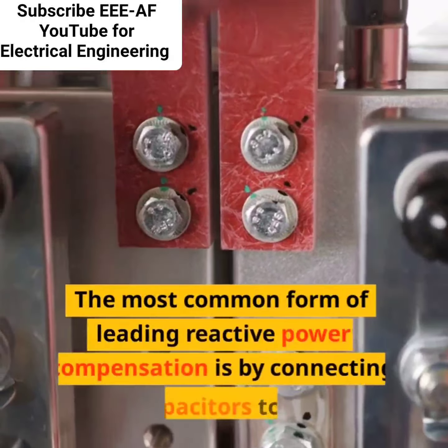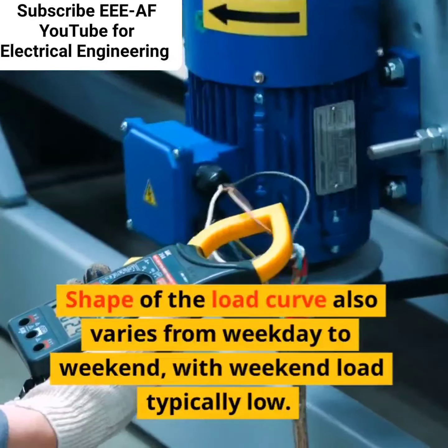Shunt capacitors. Shunt capacitors are employed at substation level for the following reasons. Voltage regulation. The main reason that shunt capacitors are installed at substations is to control the voltage within required levels. Load varies over the day, with very low load from midnight to early morning and peak values occurring in the evening between 4 p.m. and 7 p.m. Shape of the load curve also varies from weekday to weekend, with weekend load typically low.